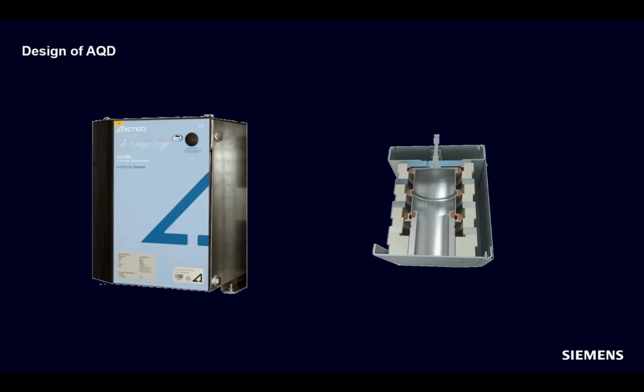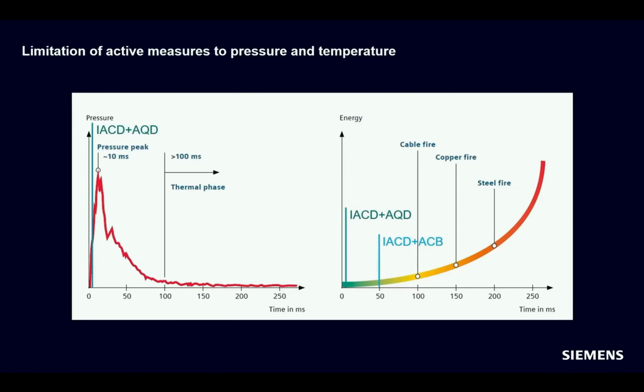How quickly does the system respond? The total triggering time from the ignition of the arc fault to its extinguishing is usually significantly less than 5 milliseconds. If we remember the pressure curve, we prevent the pressure wave from becoming so strong in the first place and causing any major damage.